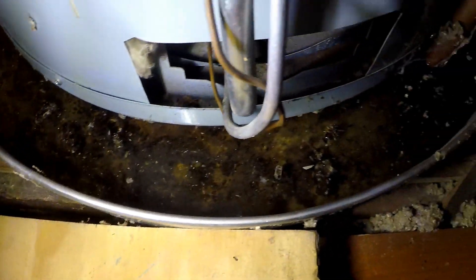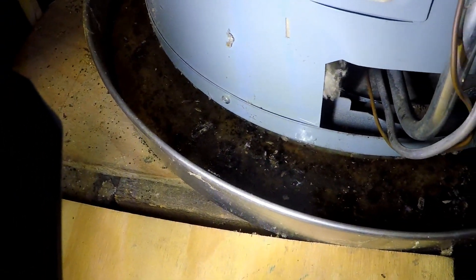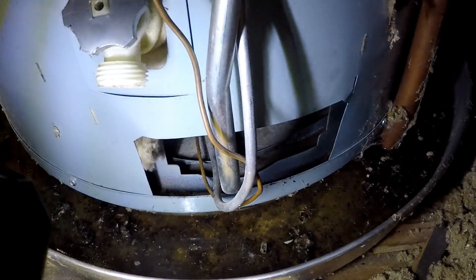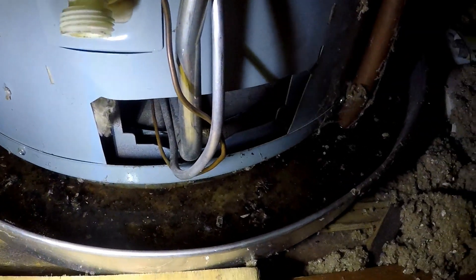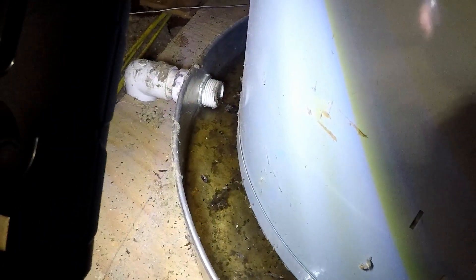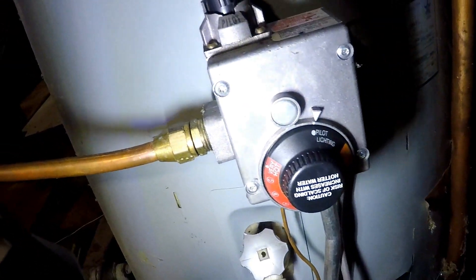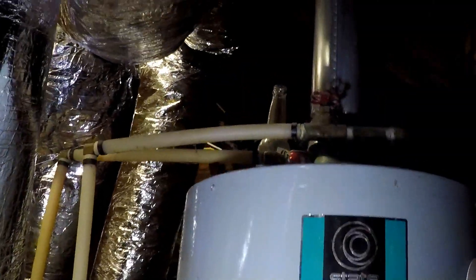There's my issue — I've got water in the drip pan. The pilot light went out. I noticed this morning my hot water wasn't as hot as normal, but it was enough to take a shower. Now coming home from work it's cool, not quite cold. The tank is full of water, and luckily there's a drain right there — it's up to the level where it's actually draining out. I tried to light the pilot light and it won't light, so this thing has probably failed.